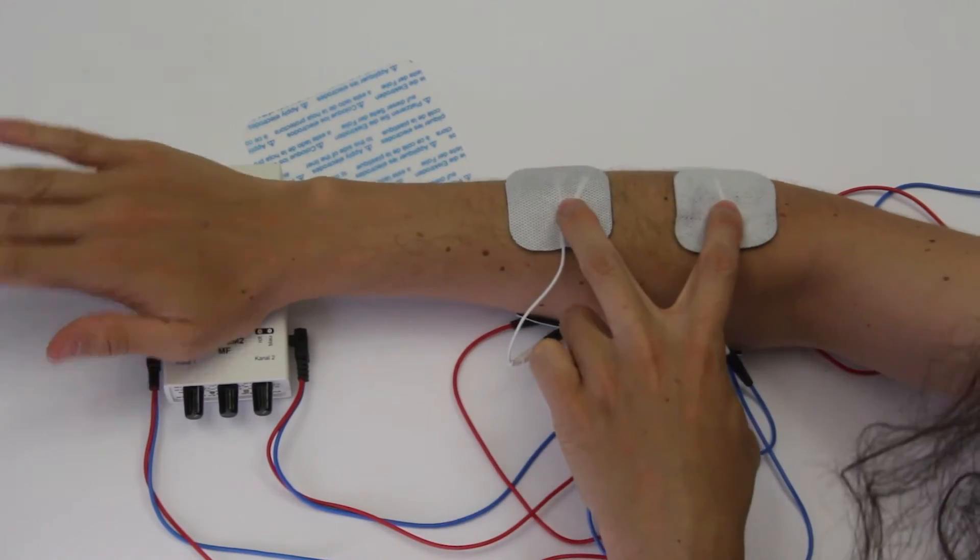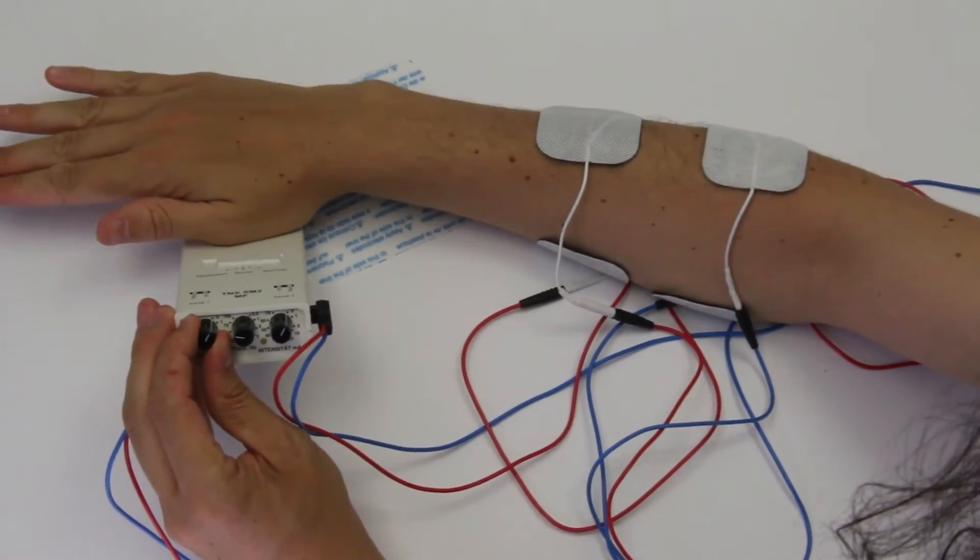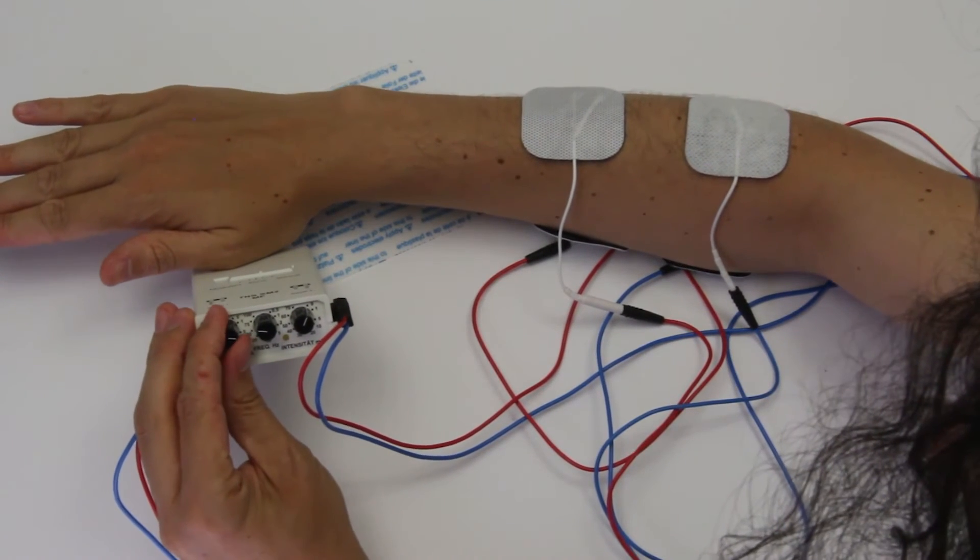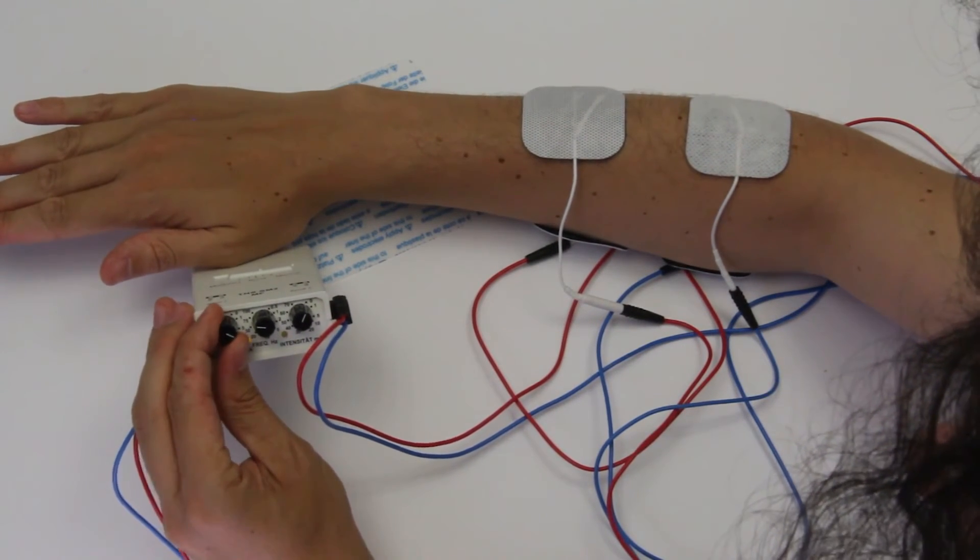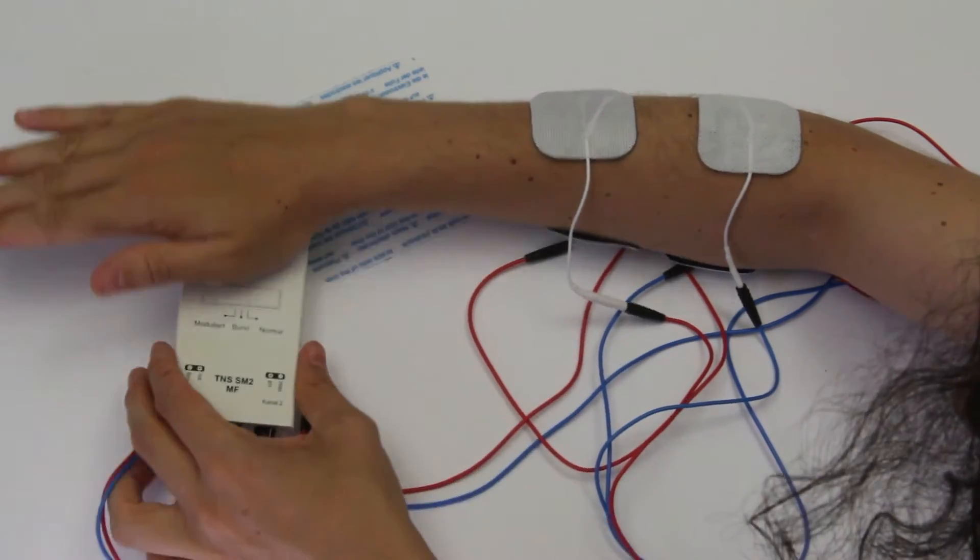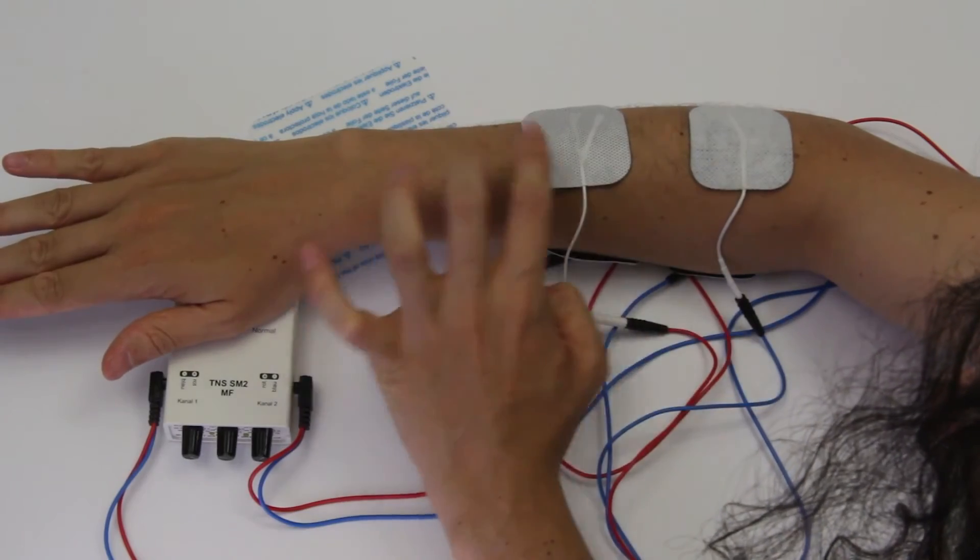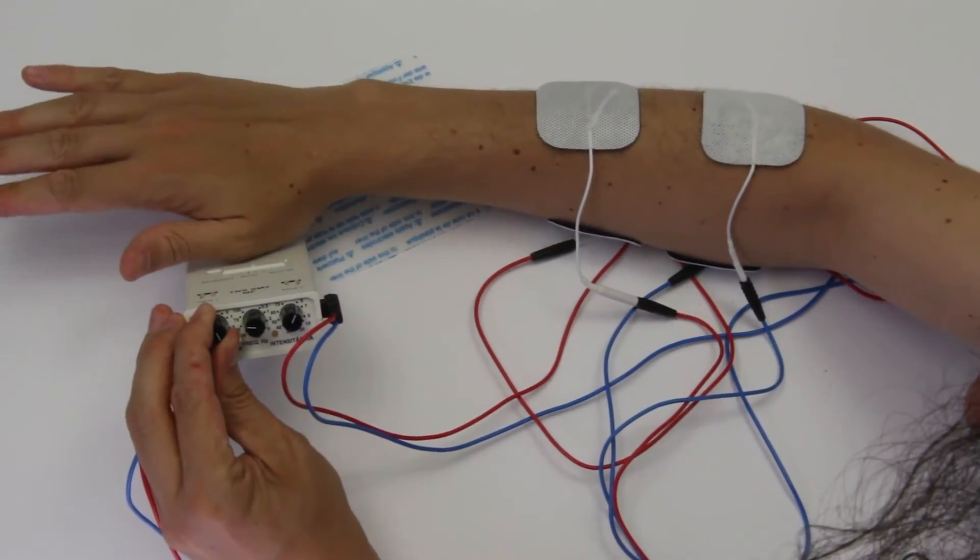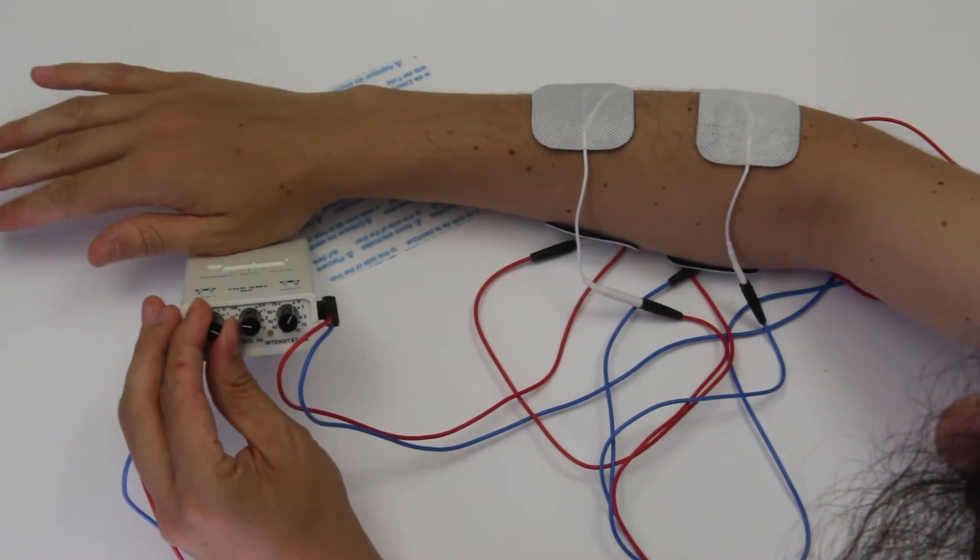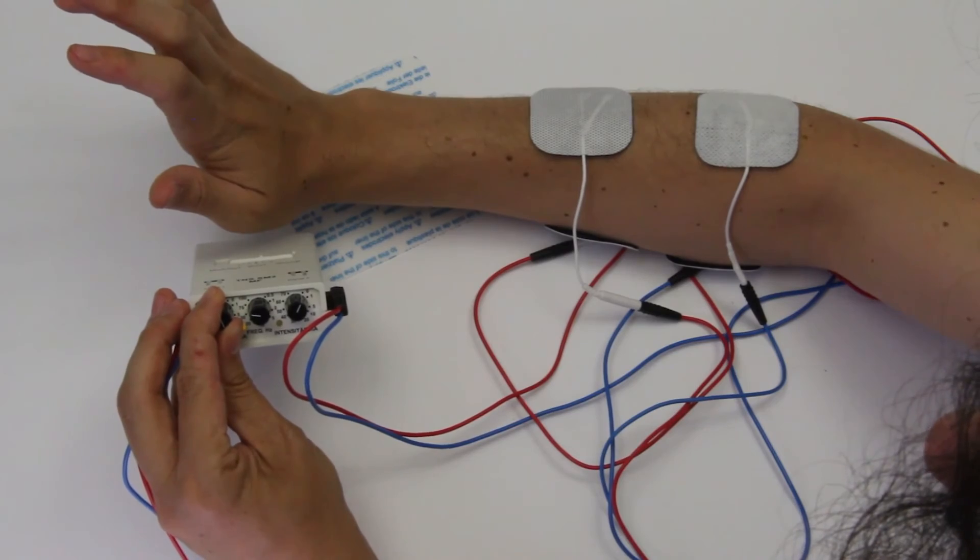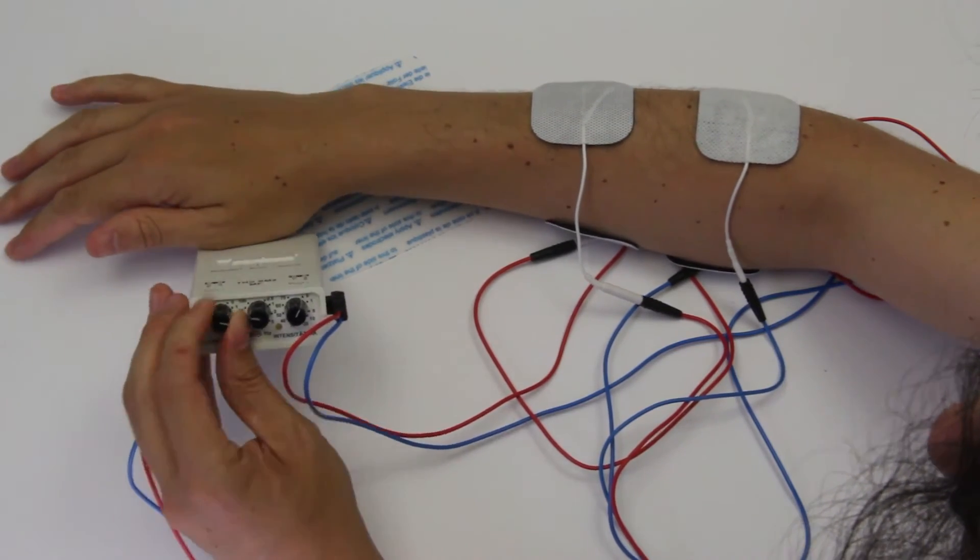I'm going to repeat the procedure. I'm opening the channel very gently and very slowly and I'll go milliamp by milliamp. At some point there's no contraction but I start to feel a tingling sensation in my skin. There it goes. And now I know that by just putting a little bit more we're going to have a motoric contraction. It elicits the muscle fibers and the muscle stimulation kicks in and my palm goes upwards. Try to find the setting that works for you.